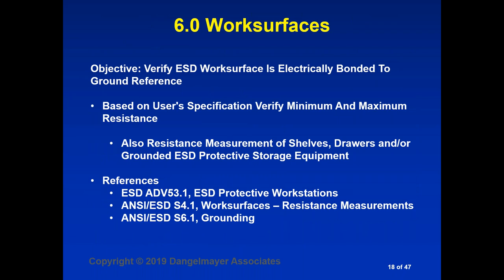So now we move to our work surfaces. We want to verify that the ESD work surface is electrically bonded to our ground reference. Minimum and maximum resistances will be specified by the end user. And we're also going to make resistance measurements of shelves, drawers, or any other grounded ESD protective storage equipment. Your references, as shown, for ESD standards: ADV53.1 for ESD protective workstations, S4.1 for work surfaces, and S6.1 again for grounding.